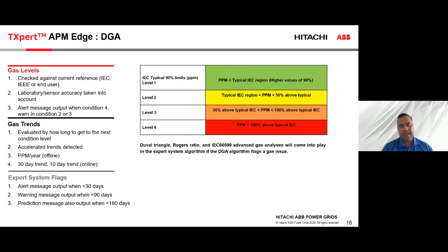The whole idea is that within 1 month's time, we have less time to react, whereas in 6 months' time, we have more time to react. So the message changes depending on how much time is available for the gases to jump from one level to another level. And finally, only when we breach either the gas level or the gas trend, we use Duval triangle, Rogers ratio, IEC 60599.